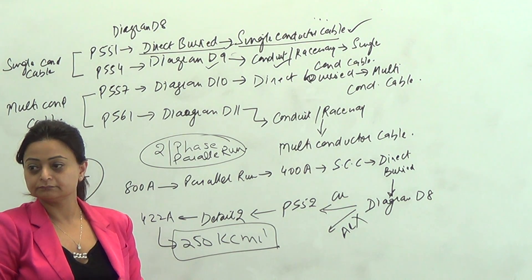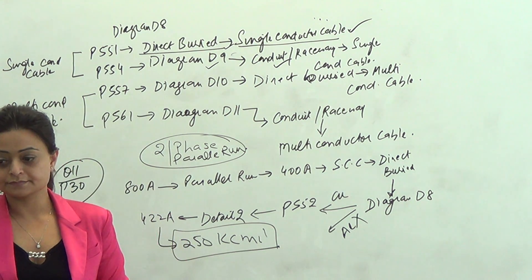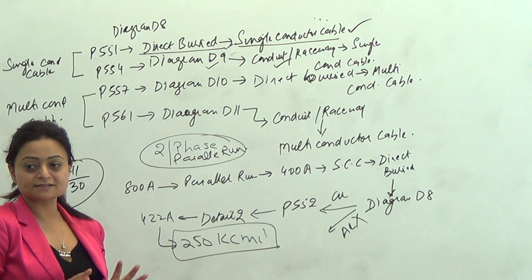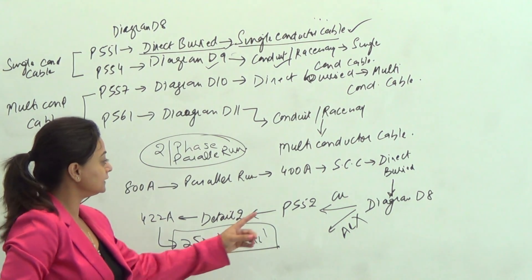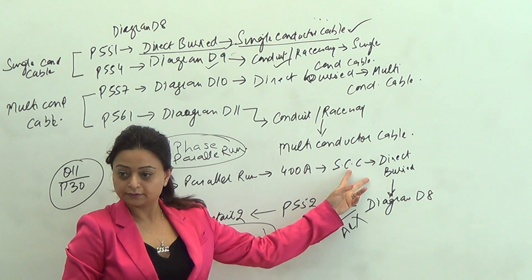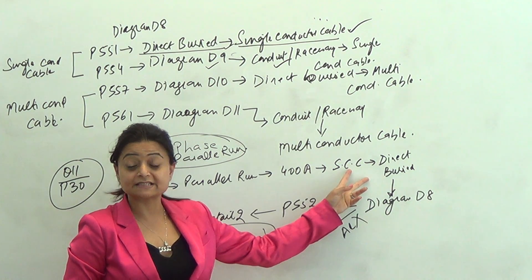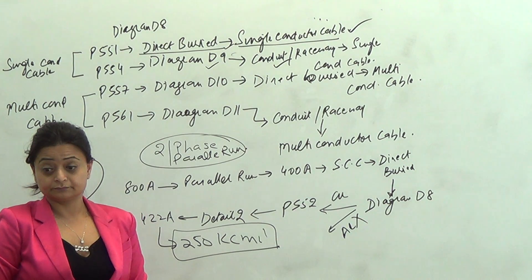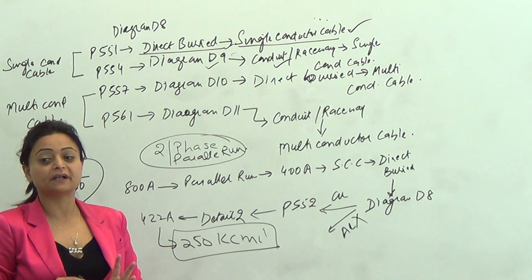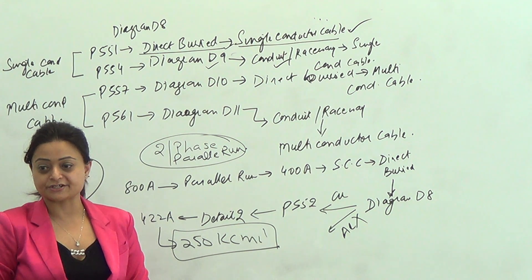Why were you guys having trouble? Are you clear now? Non-continuous doesn't mean anything here. Single conductor, direct buried, direct buried — diagram D8, detail 2, because parallel run. It says 800 amps is the total load but I'm doing a parallel run, so three key keywords in this question.